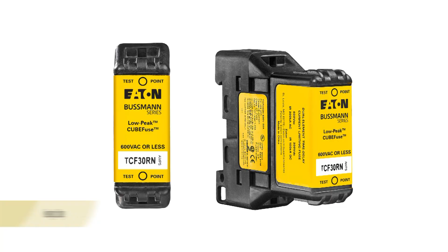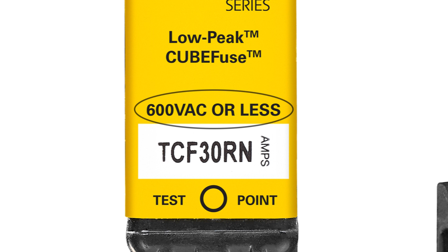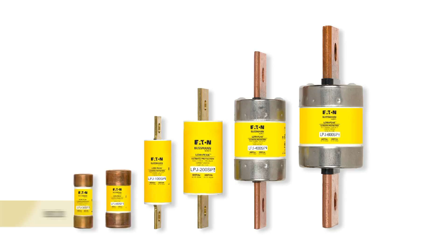These devices have been evaluated for proper performance with full phase-to-phase voltage. The fuse's voltage rating must be at least equal to or greater than the circuit voltage. For example, a 600 volt rated fuse can be used in a 208 volt circuit, but a 250 volt rated fuse cannot be used in a 480 volt circuit. Most low voltage power distribution fuses have 250 volt or 600 volt ratings.